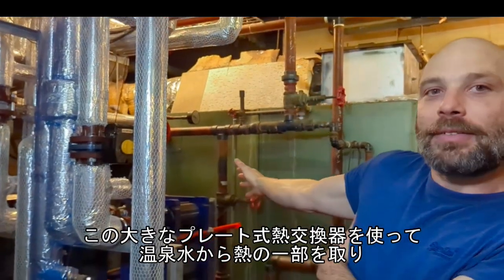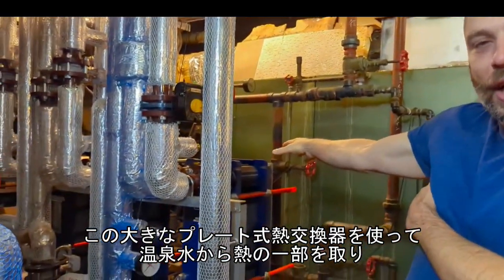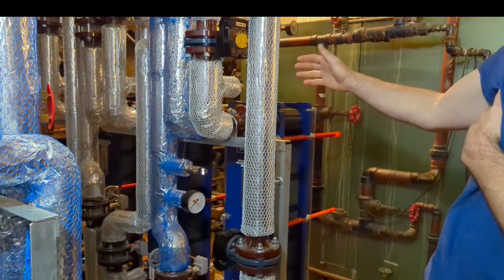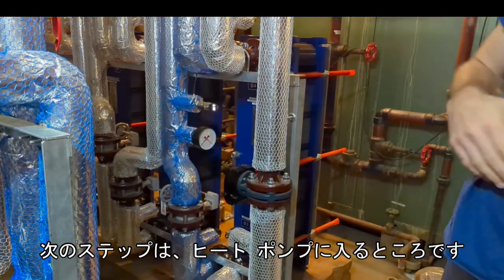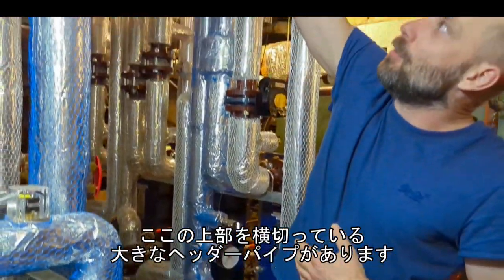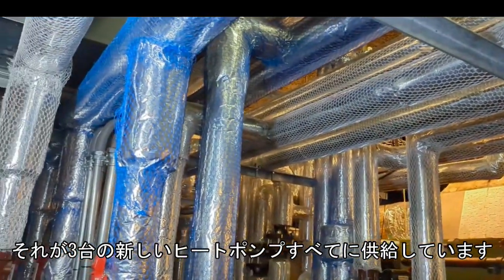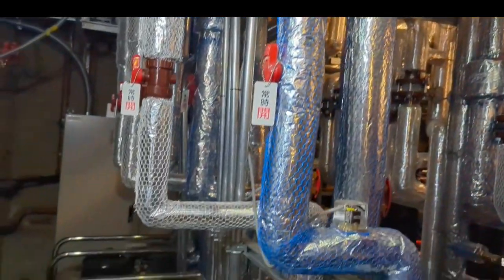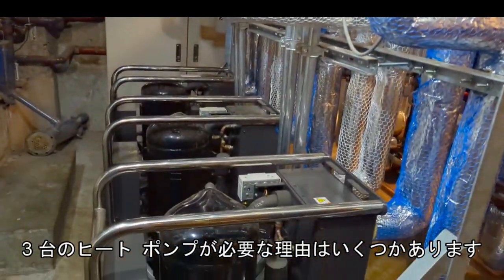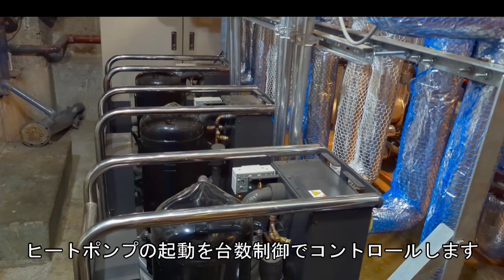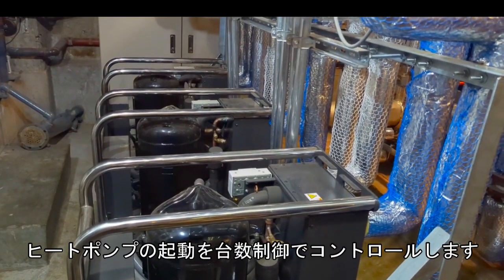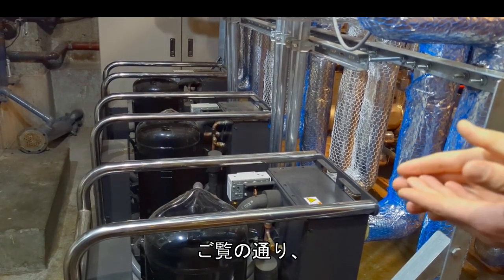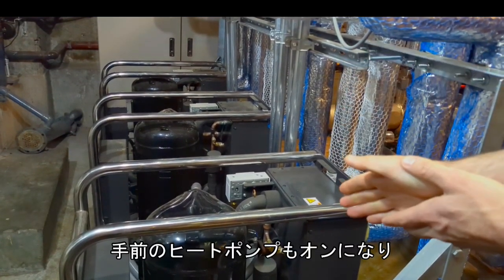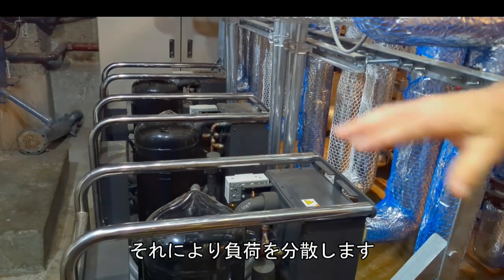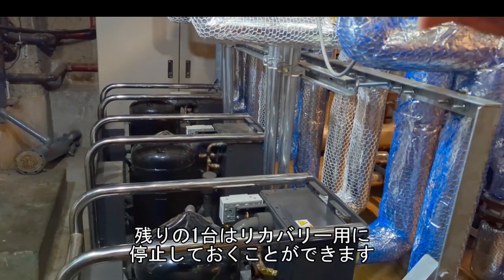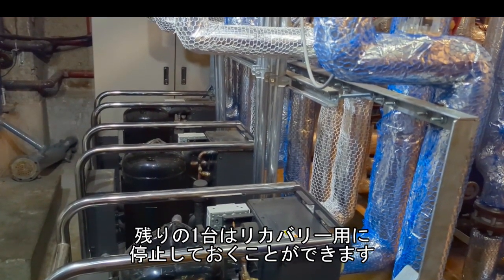Some of the heat out of the onsen water with this large plate heat exchanger, and we put it into the antifreeze. The next step is to go into the heat pumps. There's a big header pipe that runs across the top here that feeds all three heat pumps. We have three heat pumps for a few reasons. We need the extra capacity, and we can stage those pumps depending on how much heat we need to make. As you can see, it's just happened in front of us here. This pump is now turned on, the other pump is turned on, and that distributes the load, and it also allows us to leave certain units off at different times so they can recover.